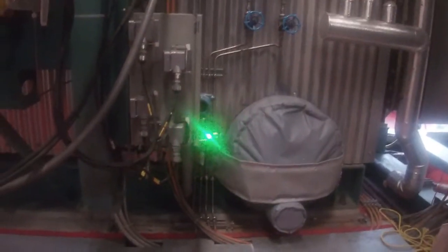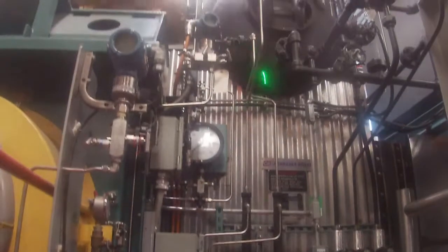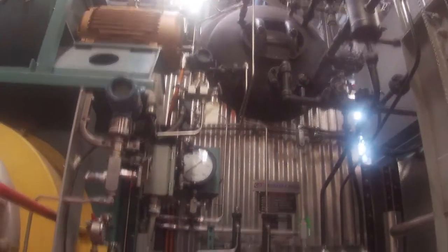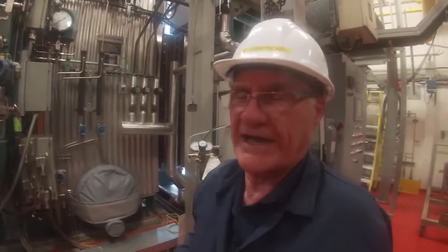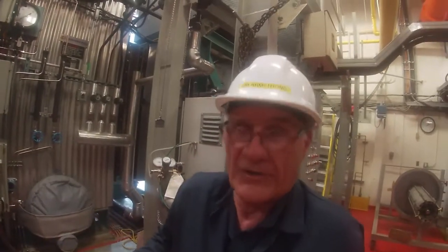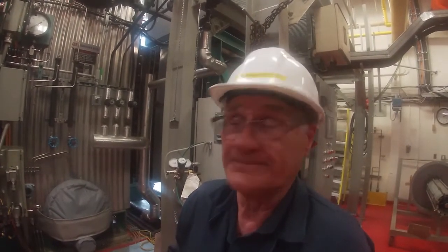The high pressure tap, where my laser is pointing right now, the H, is actually connected to the bottom of the drum, and the L that's sitting on there, the low side of the transmitter, is connected to the top of the drum. That may seem confusing, because some people might just look at it and think, well, the H has to go to the top. No, the H has to increase relative to the L to increase the output on the transmitter. Okay?